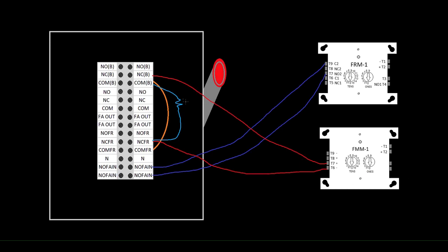It's kind of cool what they do. There's a little micro switch on this disconnect so that if you were to lose power, like let's say ComEd, if the switch was turned on like the elevator was running and you lost ComEd power, you'd get the supervisory. But if you walk up and shut power off, you don't get the supervisory because there's a micro switch on this main disconnect which is wired into one of these terminals, and it prevents the supervisory from activating when this manual disconnect is activated. And that makes sense if you think about it, because the elevator people come in and work on their elevators all the time. They don't have to consult a fire alarm company to do it. So this allows them to come in, disconnect their power to work on their elevator, and it's not going to put the panel into supervisory. Now if you lost power without the switch going, then you would get the supervisory.